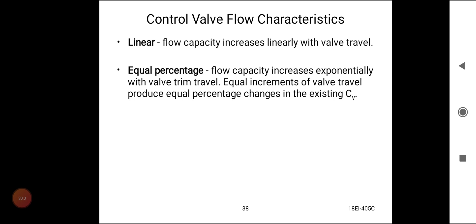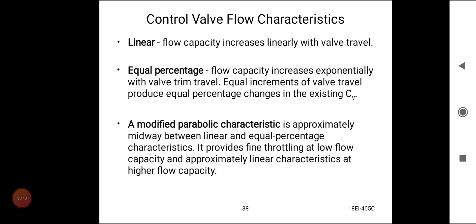A modified parabolic characteristic is approximately midway between the linear and equal percentage characteristics. It provides fine throttling at low flow capacity and approximately linear characteristics at higher flow capacity. Quick opening provides large changes in flow for very small changes in lift. A small change in the lift of the stem causes a large change in the flow of fluid passing. It usually has too high a valve gain for use in modulating control, so it is limited to on-off service such as sequential operation in batch or semi-continuous processes.